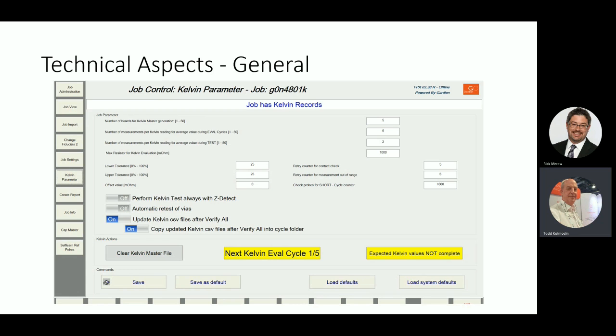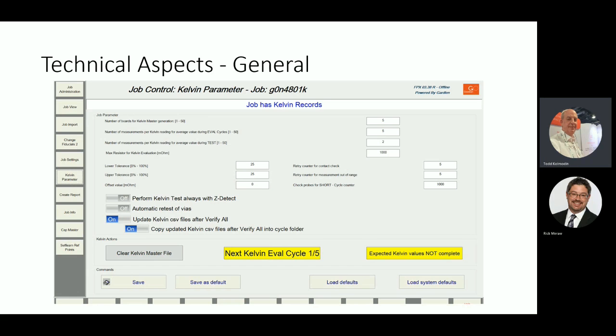One thing to mention here, when we're looking at this screen where we talk about our tolerance upper and lower, some people might be thinking, well, what does it matter on the lower tolerance? If you have zero resistance between the 2 points, isn't that totally acceptable? And I would say, in most cases, you're absolutely right - that tolerance really has no significant effect overall, when you're looking for a certain resistive value with an upper tolerance allowed.